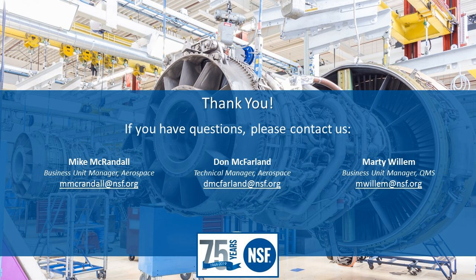And really what the calibration house or the external provider needs to provide is some evidence that their processes are then traceable back to a standard that's more resolute, more finite than the tool that they're calibrating, right? They've got that 10-to-1 ratio met. So if they can do that by a statement that says our tools are traceable to NIST, that's great. That's their process. If they say we do it in accordance with our procedure, and here's the serial number for the assets that were used to perform this calibration or verification effort, that's perfectly acceptable as well.